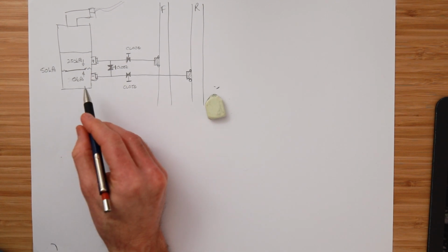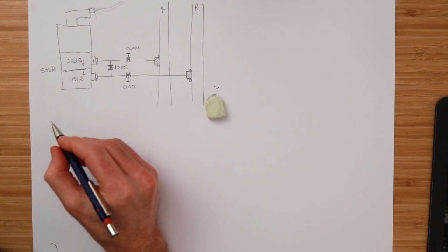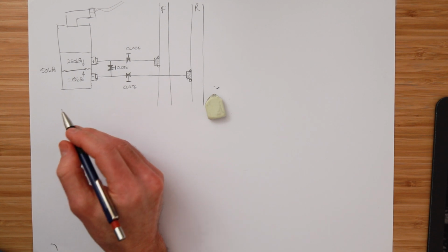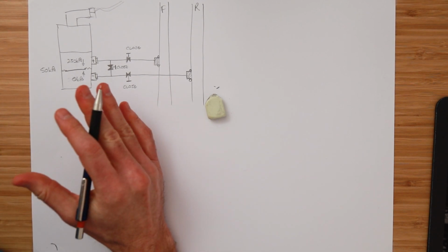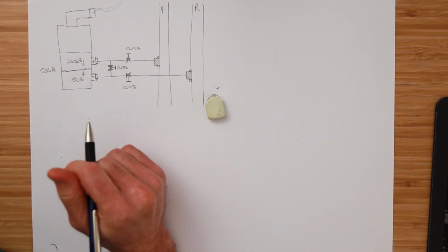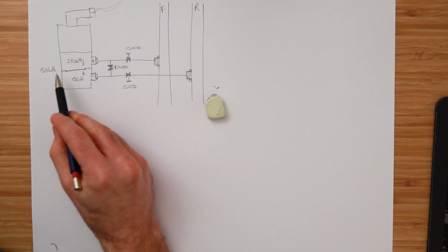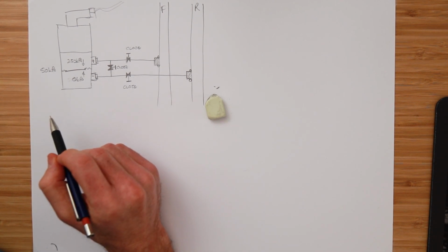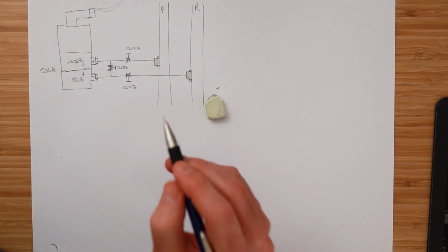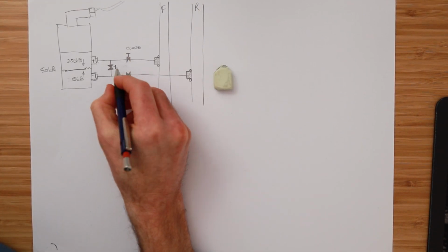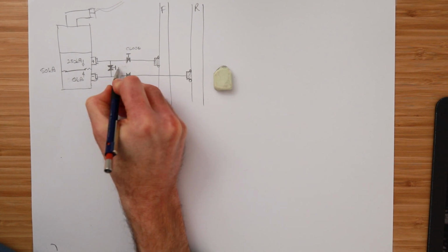I used to get so frustrated with this that I'd almost sarcastically be saying to my colleagues, you know what, I'm going to buy 2 pressure transmitters for all the chillers on every job because the mechanical guy bursts the diaphragm every single time. That's why this valve is here. What you're supposed to do is this. The mechanical person should first open the bypass first.